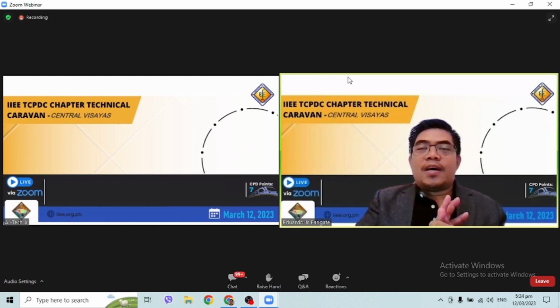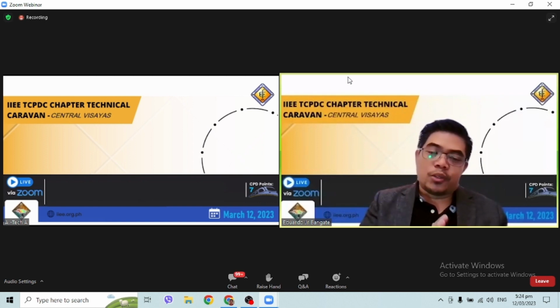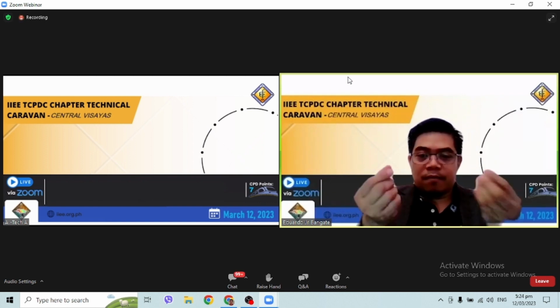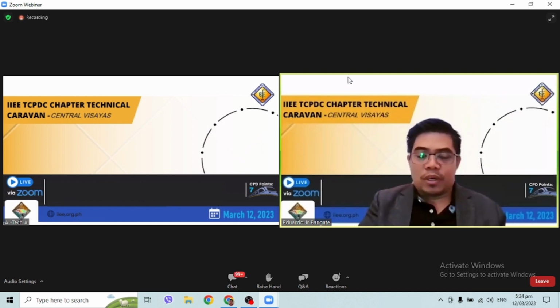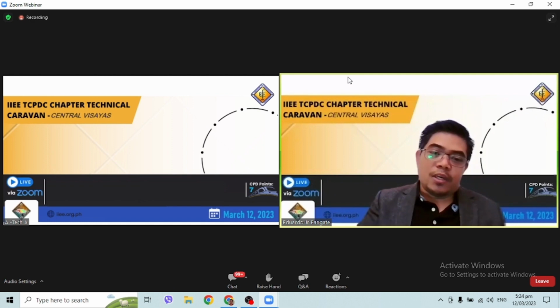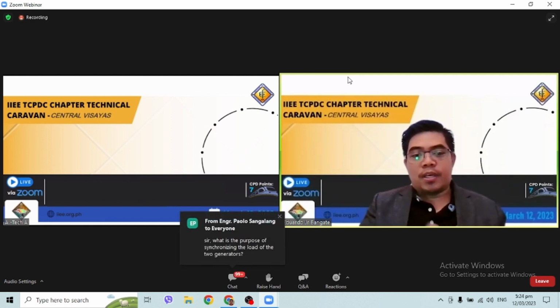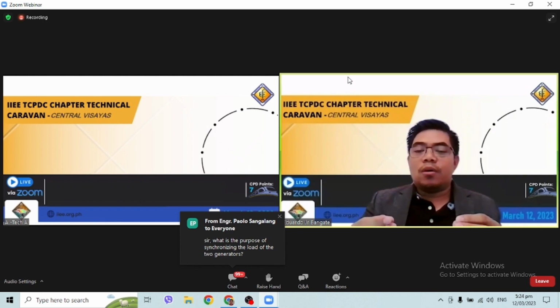And the checklist, we have the checklist as recommended by the manufacturer. Every manufacturer includes the checklist in their book whenever they deliver a generator to the customer. So you have to follow those checklists, the pre-delivery inspection checklist, and operate the generator. Make sure that it is operating according to what the manufacturer is saying.